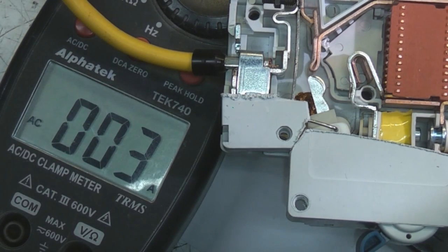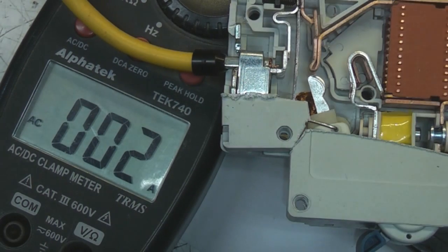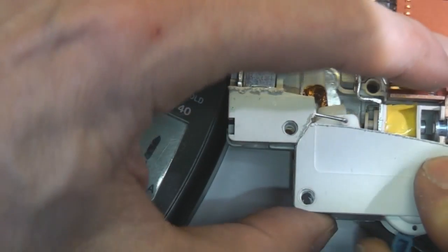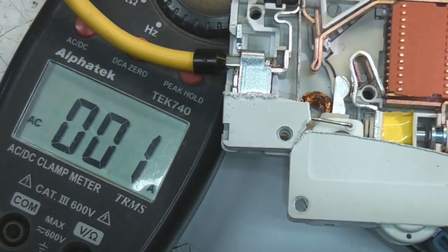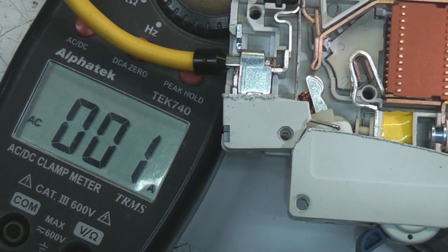So now if we look at the magnetic side of things, I'm going to turn the variac fully up, so this will put about 280 odd amps through as soon as I hit the switch. And what we should see here is that the strip won't have time to move. This magnetic mechanism will just trip it out pretty much instantly. So if I just turn this on, bang, instant trip.